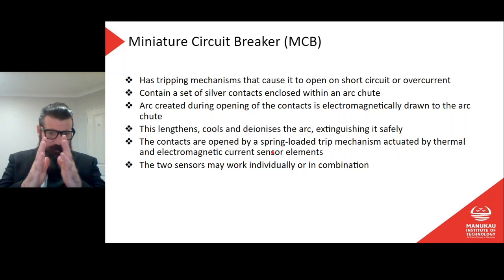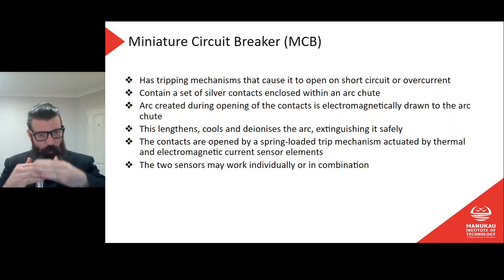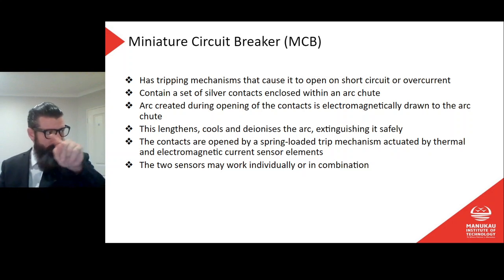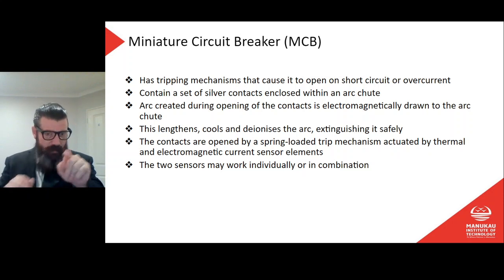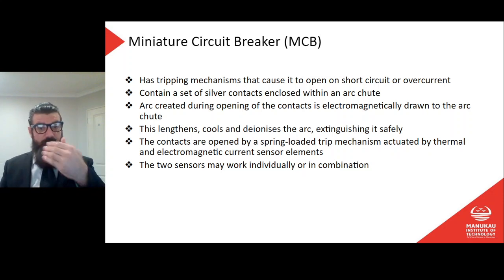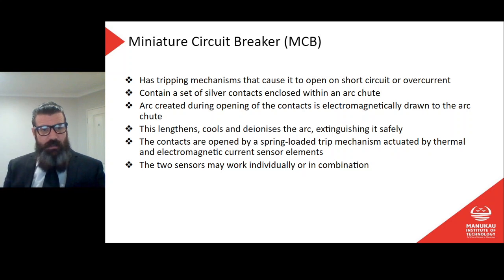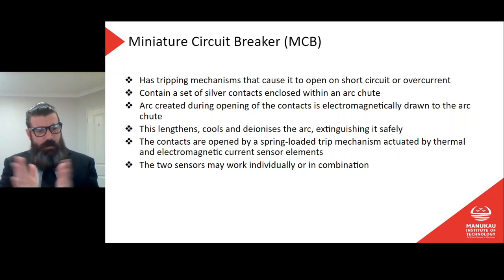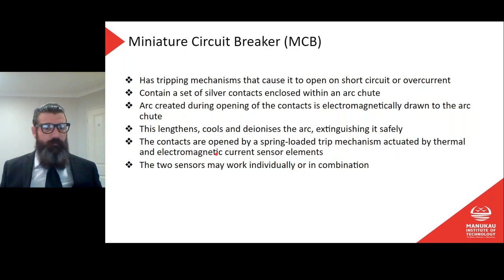In addition to that, we have the arc chute, which is like a bunch of little plates close together. When it opens, the arc gets directed between the little plates, and each time it jumps across, it's taking more and more energy to create that arc, so that reduces the energy of each arc, and will extinguish the arc. As we saw in the last video, once our arc is extinguished, the circuit is now protected. We've shut that circuit down, opening those contacts. Okay.